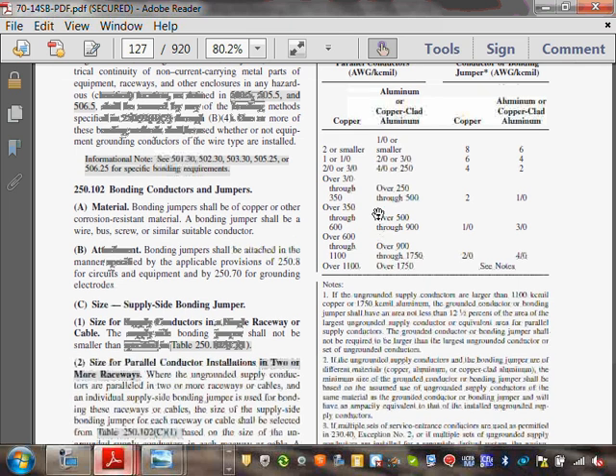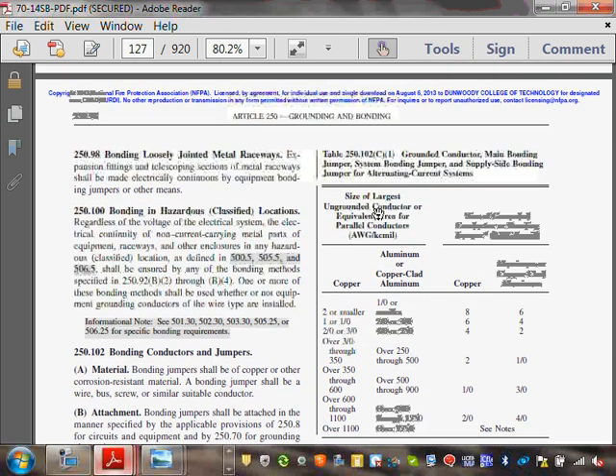Here's another table. Welcome the 250.102(C)(1), the newly created table. Look at all the stuff that I gave you guys on that sheet. It makes it easier now. It used to be really hard. For example, can you guys see this table? It tells you grounded conductor, so you can use it for the grounded conductor. Remember when I said you size the grounded conductor not smaller than a main bonding jumper? Now it tells you can use it for the grounded conductor, main bonding jumper, system bonding jumper, supply side bonding jumper, and for AC systems only, not DC systems. So they made it really easier, the title.